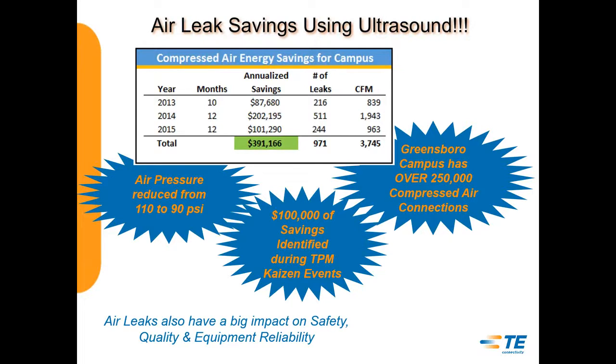So I know basically how much electricity I spend to generate so many horsepower of CFM, and I know about how many CFMs come through different orifices, so I know about what the dollar amount is. And the numbers from the IntelliFlow system and the UE system typically tie back pretty close. So it is a very good spreadsheet, and it's been one of the biggest things to help us get resources and quantify our savings in a way that we can actually defend.